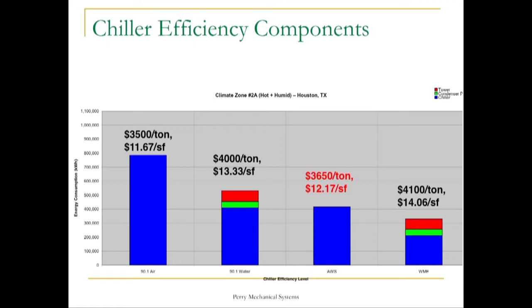Now, if you go to one of these premium efficiency air-cooled machines we were talking about, you're actually less expensive in dollars per ton than you are water-cooled. So it's lower installed cost, and you're even more efficient. You see, you're almost half the energy consumption of your baseline, and you're at $12 a square foot on your building. And this here is your condenser water side of the water-cooled machines.